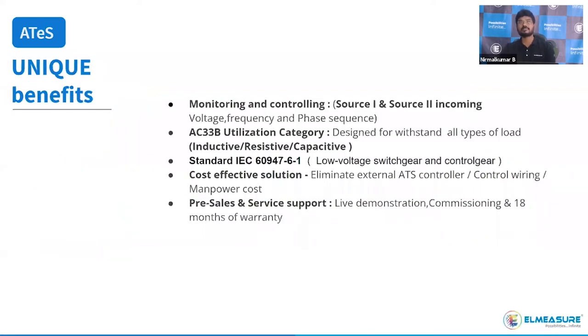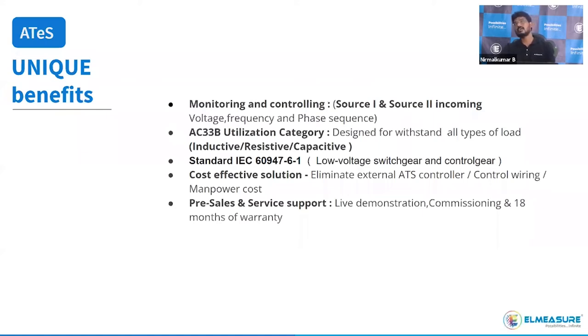A unique benefit is monitoring and controlling for both source one and source two — voltage protection, frequency protection, and phase-sequence protection. While competitors focus only on controlling, our ATS includes monitoring via a remote display where you can monitor incoming three-phase voltage and frequency. Optional current monitoring is also available, eliminating the need for an external multifunction meter. All protection and monitoring devices are in-built.